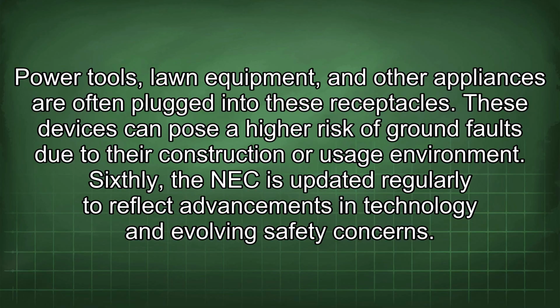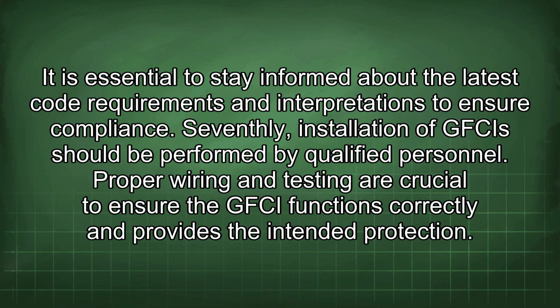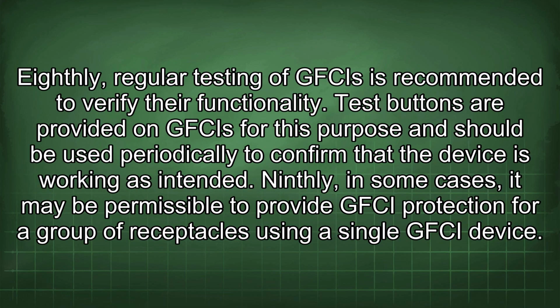Sixthly, the NEC is updated regularly to reflect advancements in technology and evolving safety concerns. It is essential to stay informed about the latest code requirements and interpretations to ensure compliance. Seventhly, installation of GFCIs should be performed by qualified personnel. Proper wiring and testing are crucial to ensure the GFCI functions correctly and provides the intended protection. Eighthly, regular testing of GFCIs is recommended to verify their functionality.